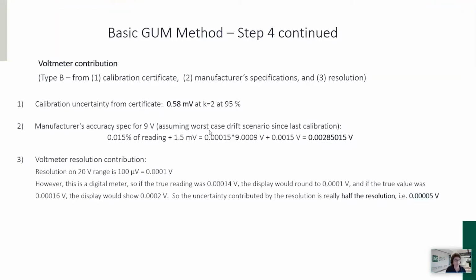And so we don't know exactly what this drift is at 9 volts. So we're assuming the worst case drift scenario since the last calibration, because we send our equipment out to be calibrated, and it's calibrated to the manufacturer's spec, which we assume it is in this particular case, then we can use that as a worst case drift scenario. And here the manufacturer spec is 0.015% of reading plus 1.5 millivolt of the full scale spec, and that will give you roughly about 2.9 millivolt. So that's what we get from there.